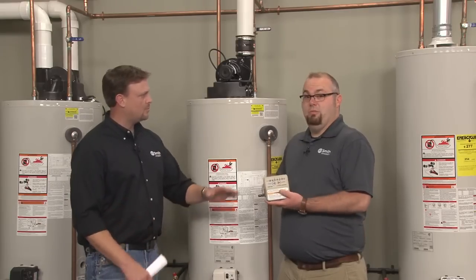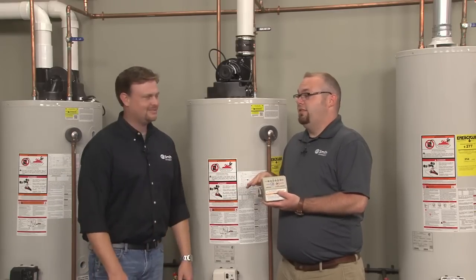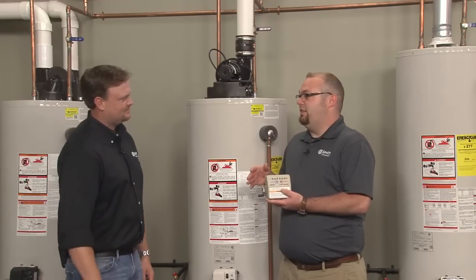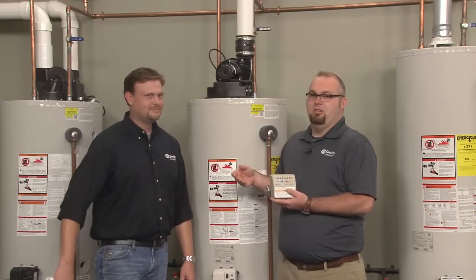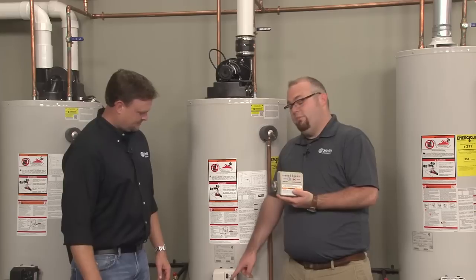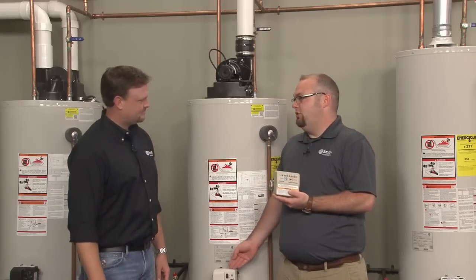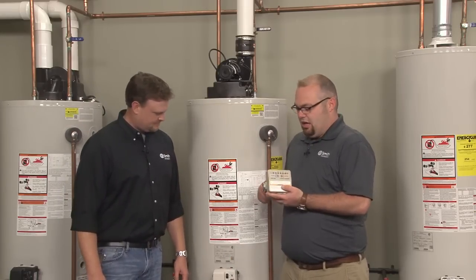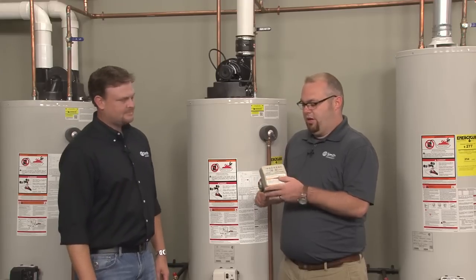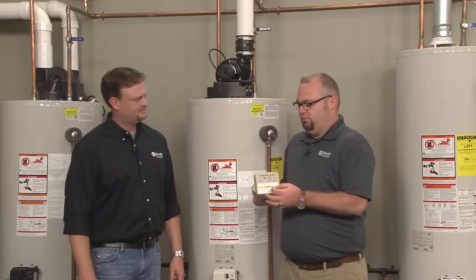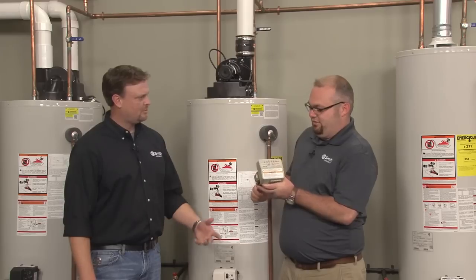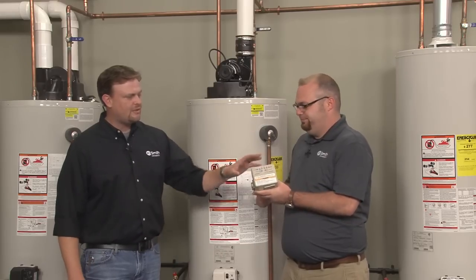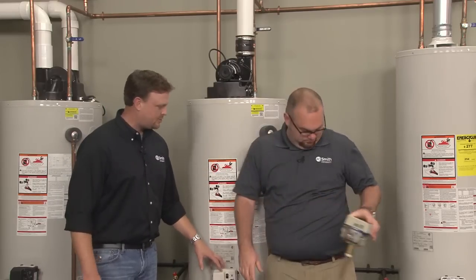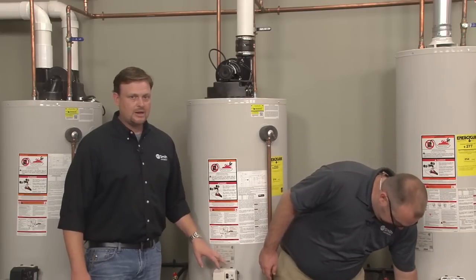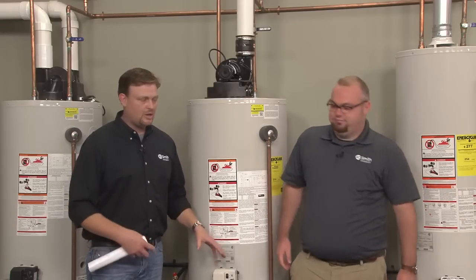The temperature's going to be at the last point it was. All right. And so that's a good thing I like about the IntelliVent, that the temperature is really not going to change. This one, you should always set it back to hot, 120 degrees, unless you have a mixing valve. The reduced risk of scalding, but yeah, same thing. All right, cool. So you'll have to reset both of these if you do run into a flammable vapor lockout situation. Then you will have to reset both of them.